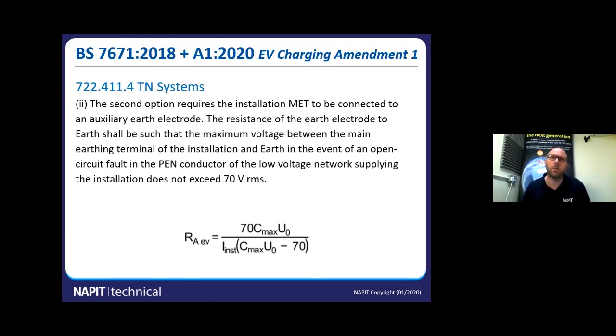We have to use the Cmax formula because the voltage is allowed to be distributed with a plus or minus allowance. It's allowed up to 10%. So if we add 10% to our 230, we get 253 or whatever it is. So we need to use a Cmax factor of 1.1. So it's 70 times Cmax times U0, which is 230, and we divide that by the bottom. Now, I've explained all the stuff on the right hand side. The INST is the installation's maximum demand plus the EV charging load. So it looks complicated, but it's a fairly easy formula to do.